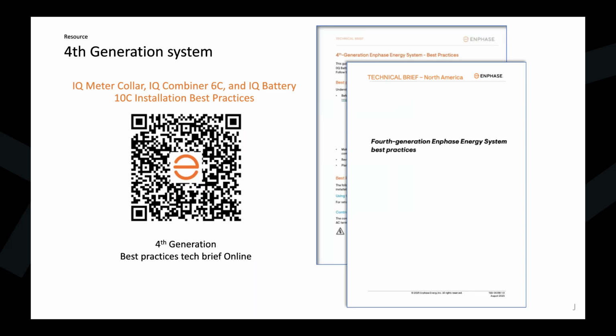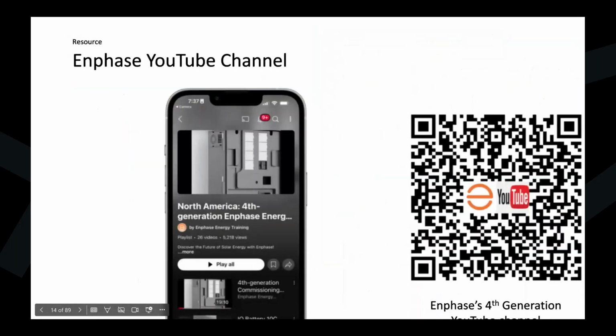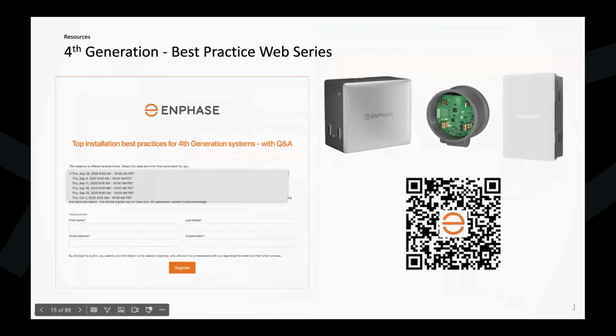So what happens when you drain the battery cell pack? Irrecoverable battery. So the bottom line is, the way we're instructing you all is that if you don't have PTO or you're not leaving the system in the operational state, especially if you aren't commissioning, disconnect the DC, disconnect the micros from the batteries, those microinverter plugs from the batteries, and disconnect the switch, but make sure the switch is in the off position.